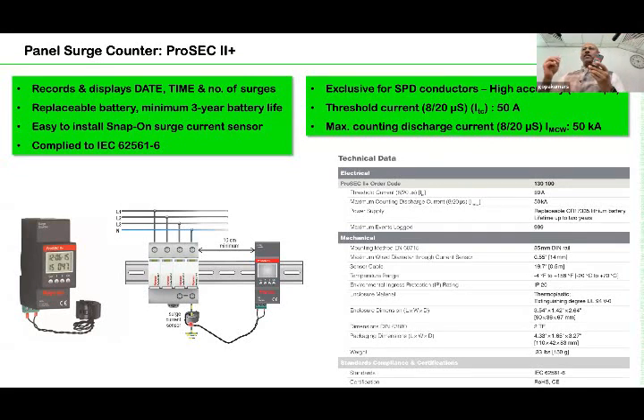So say, for example, Wednesday afternoon, 2 p.m., there is a surge. Maybe on the same day there are 20 surges. All these things can be recorded. This becomes a very good tool to decide whether the SPD is really working or not, because SPDs are passive devices. Nobody knows whether it is working or whether there is a real surge or not. The advantage of this device is that if the surge current is more than 50 amps, it starts counting. Even with a very small surge, it counts.